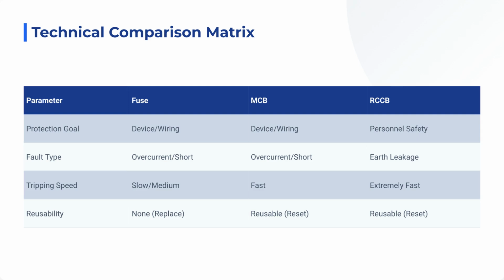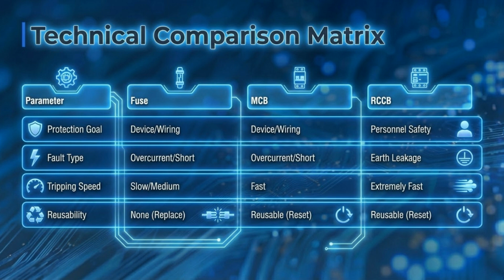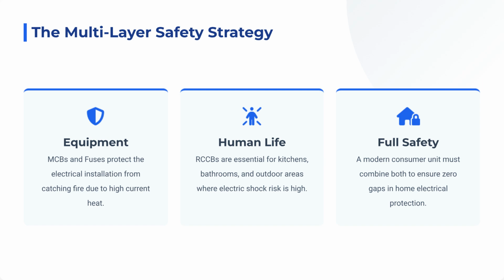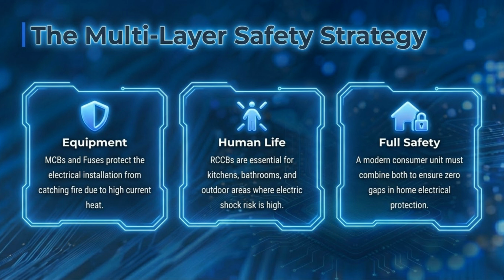Fuses and MCBs protect the device and wiring, while RCCBs prioritize personnel safety. The chart shows differences in fault type protection, tripping speed, and reusability, highlighting the unique role each device plays in a safety system. A multi-layer safety strategy is key. MCBs and fuses protect equipment from overcurrent, while RCCBs protect human life from electric shock. Combining these technologies in a modern consumer unit ensures zero gaps in your electrical protection, offering full safety.